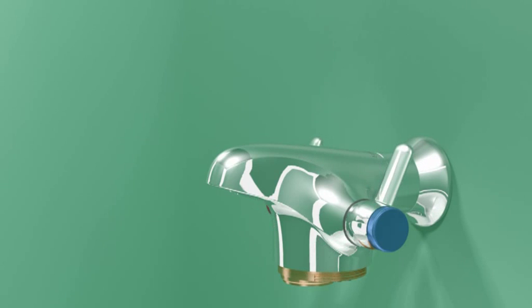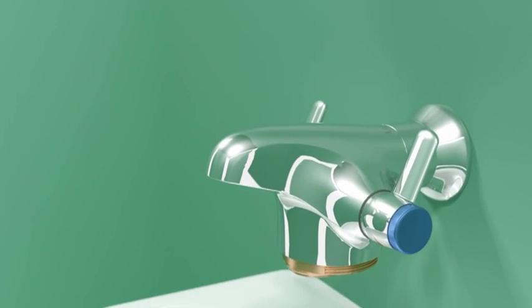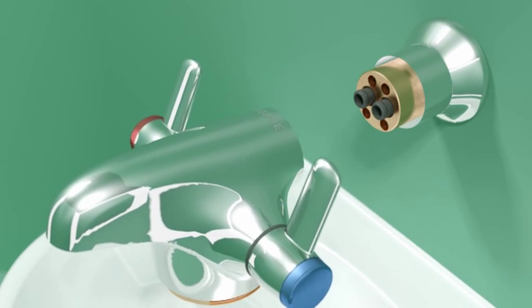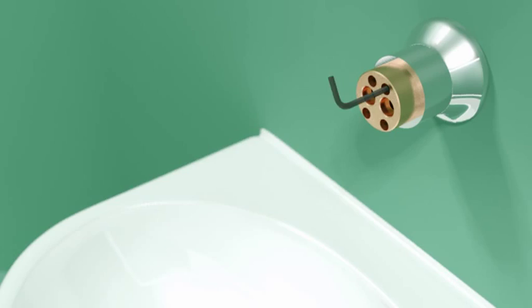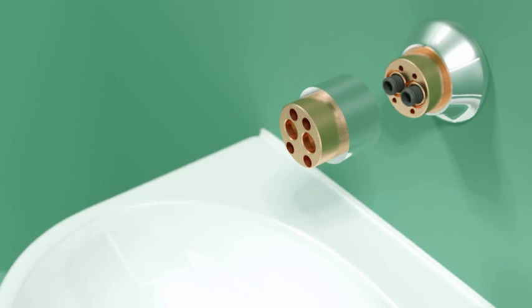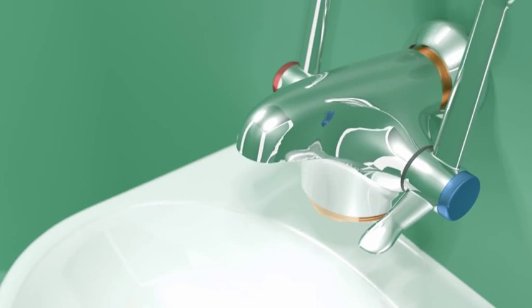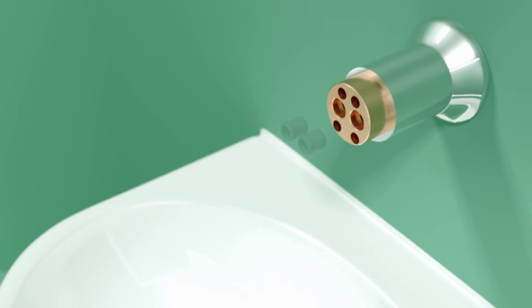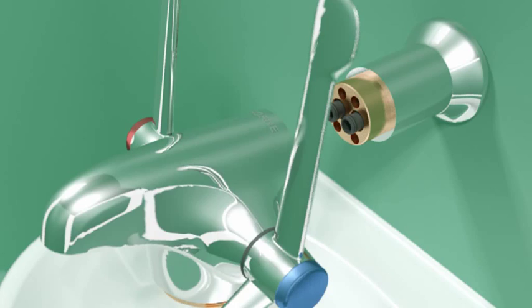The single short lever variant of the OptiTherm is suitable for installing over a bath. Unscrew the four M5 screws and washers to release the existing extension piece from the spigot. A tap cannot be installed without an extension piece. Offer the longer extension piece up to the tap spigot, making sure the interconnect nozzles are correctly positioned. Secure the extension piece with the four M5 screws and washers.